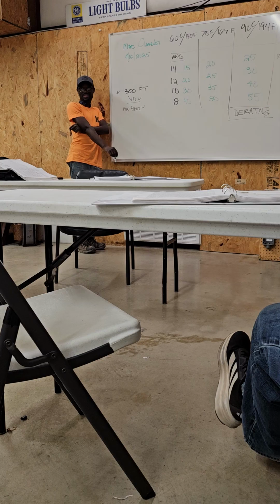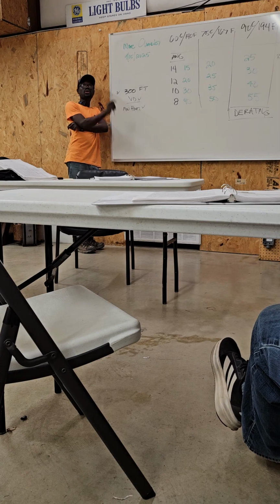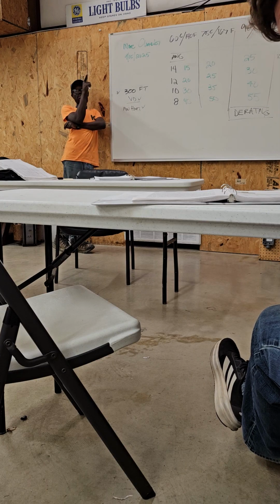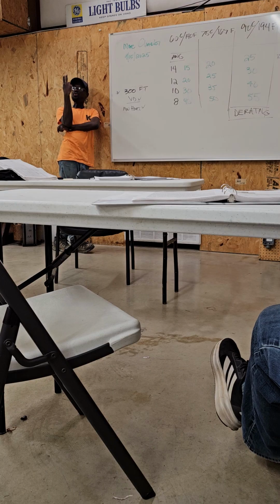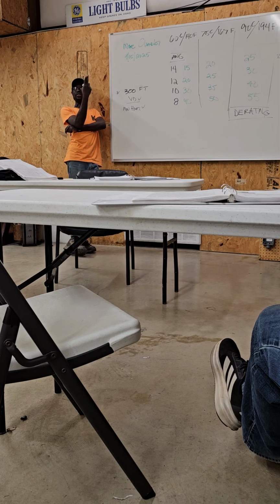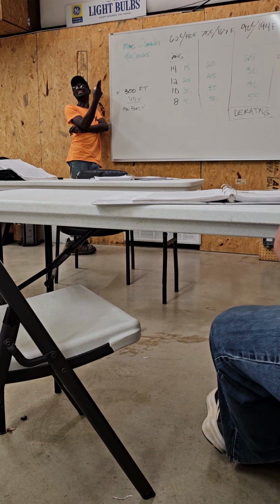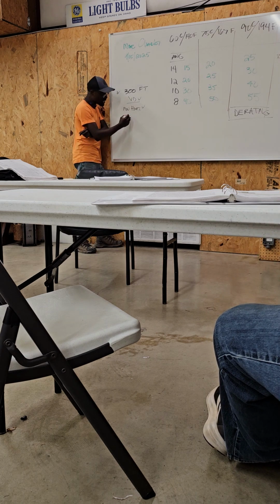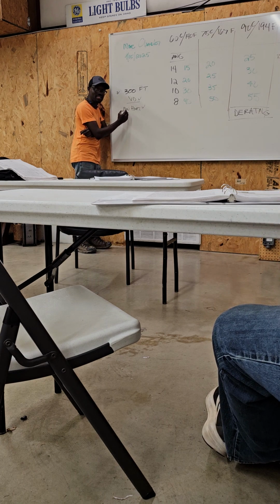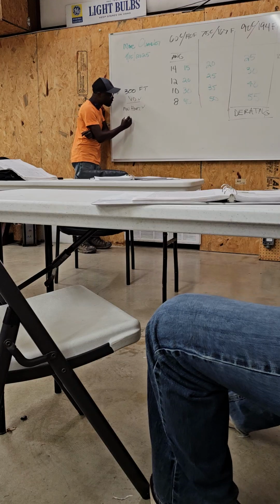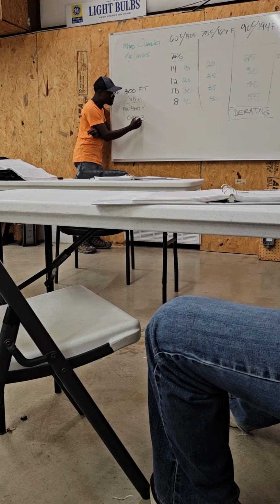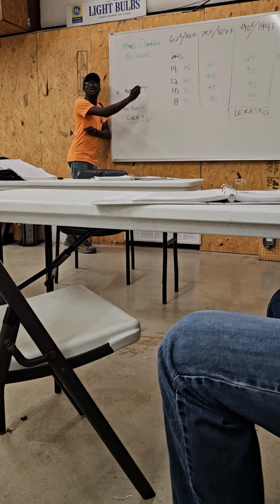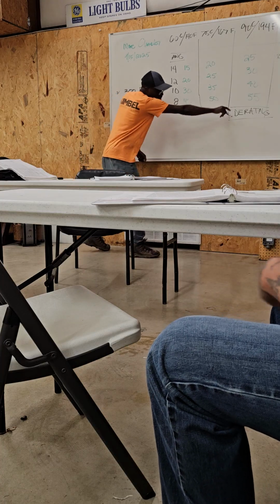Guess what the third one is? My boss will kill me if I only pull two little wires inside this pipe. He said, you better pack this baby up, put as many wires as you can in there. If I have a 1-inch pipe, there's going to be at least 10 number 8 in there, minimum. So now I have over 3 conductors. Strike 3. That's why we use that column.